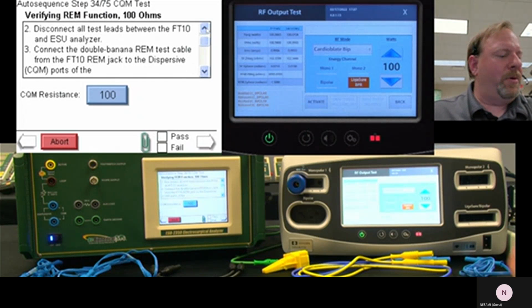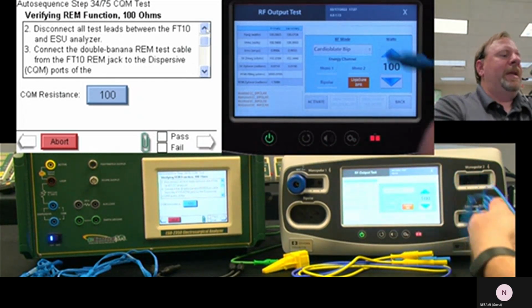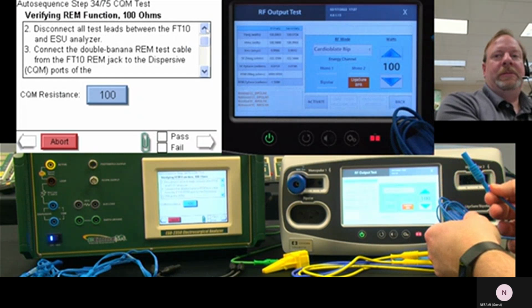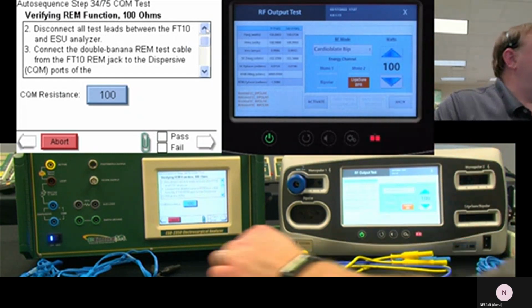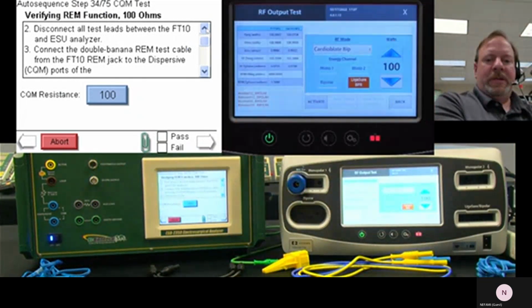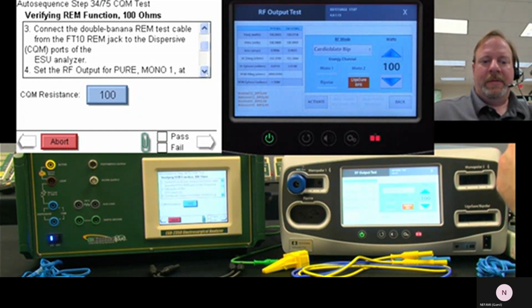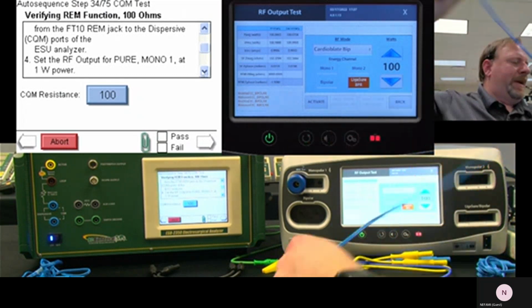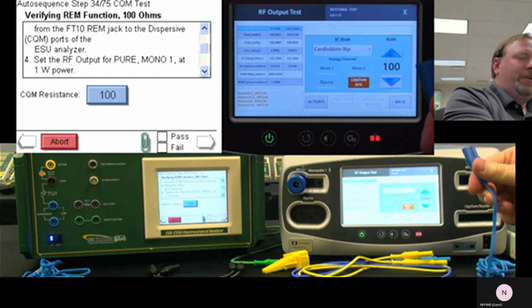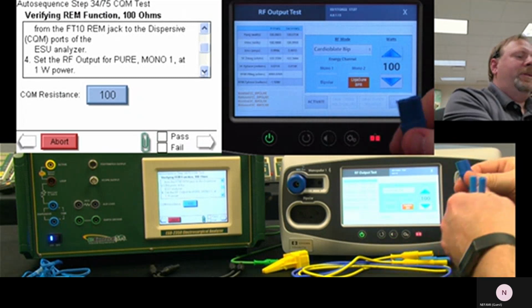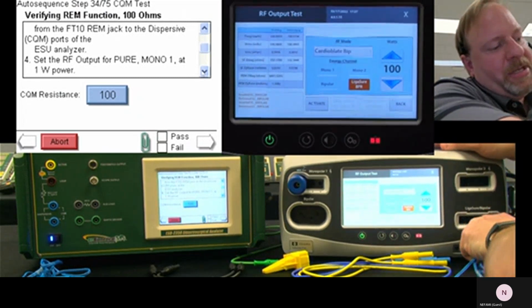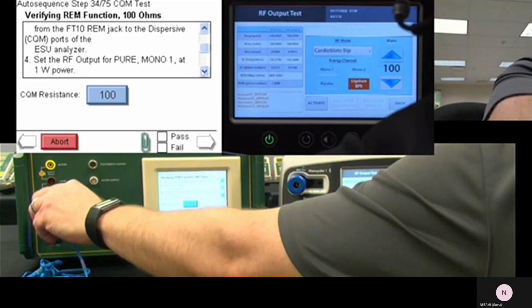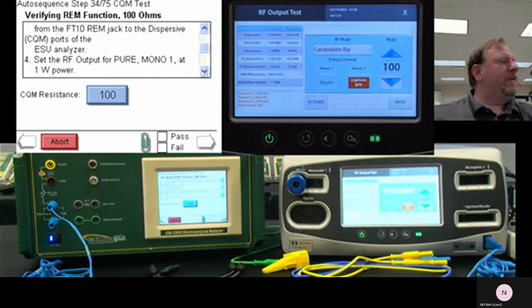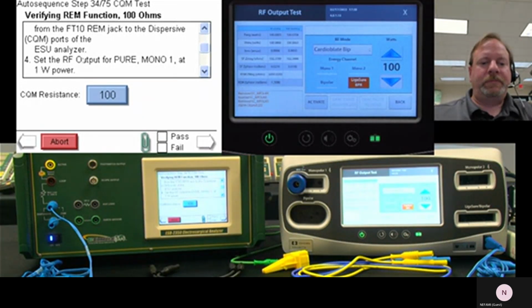So it was important to note that we did say double, because in this kit there is a single banana REM cable. We don't want to use that one. But again, because we're using the double banana, we'll see what happens. I think because we're in the special test mode, it doesn't matter whether we have the pin or not. So I am purposely going to use the one without the pin just to see if it really does work. Now in clinical mode, this cable would not work. But we're not in clinical mode, we're in test mode. We're just checking the resistance.